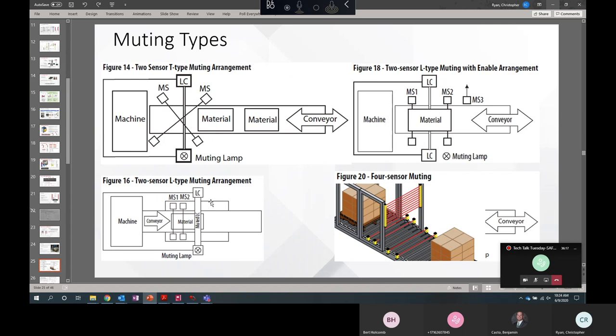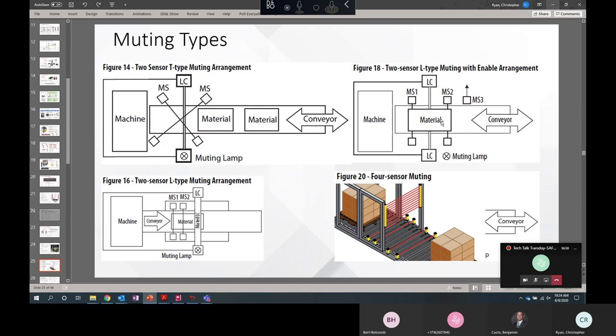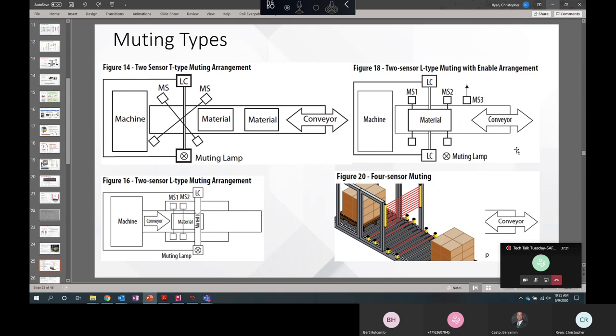Bottom left, we've got the two-sensor L-type. This is probably the most common type that I see in the field. We have a palletizer or a boxer or a taping machine or a press or something that's making parts. Stuff is coming out. You want your pallets and your material to come down the conveyor out of the machine. We don't want humans to go in and get hurt. So they set up two sensors here and arrange muting that way. This top right muting arrangement is the only type that requires Connected Component Workbench to configure. This is used if you have a periodic or maybe a very small package that's coming out that's not the same. So you'd have a signal here. Muting sensor 3 would be a signal either from an operator or it could be from the conveyor itself. The muting sensor 3 or the enable would have to turn on at the same time as this sensor to let the material go this way and then vice versa to come out. And then the bottom right, we have our four-sensor T-type muting, which is similar to the two-sensor L-type, except it moves in both directions.